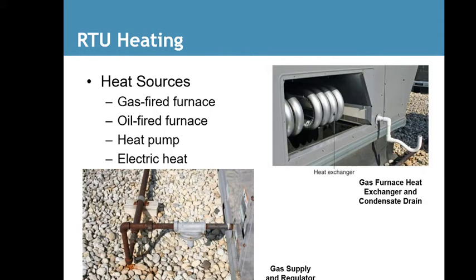Now, if you're up in the Northeast, where it can get below 0 degrees, it's something that you need to think about when sizing a unit. But most companies, if it's an office building, don't use a lot of heat, because with computers and employees and lights and all those things that make up an office, usually air conditioning will run most of the winter as well.